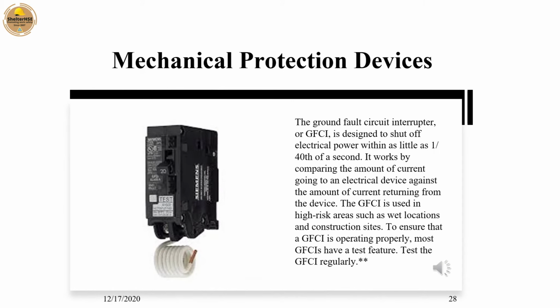The ground fault circuit interrupter, or GFCI, is designed to shut off electrical power within as little as 1/40th of a second. It works by comparing the amount of current going to an electrical device against the amount of current returning from the device. The GFCI is used in high-risk areas such as wet locations and construction sites. To ensure that a GFCI is operating properly, most GFCIs have a test feature.